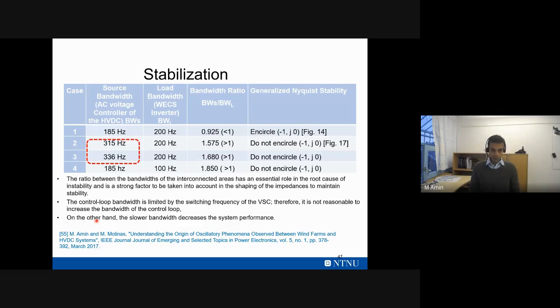This is an example where we change the controller bandwidth for the HVDC system - we increase it to make the AC voltage control loop faster. We see that it no longer encircles the critical point, so the system becomes stable if we increase the bandwidth of the AC voltage controller.